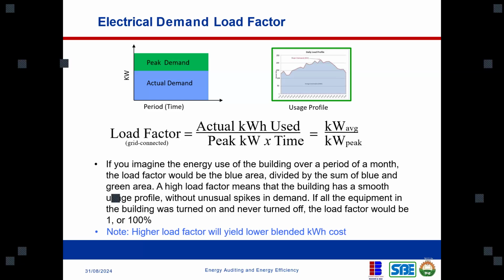So let me give a typical example. If you go into a facility and you see a peak demand in that facility, and that peak demand is, for example, 80 kilowatts, and this demand happens only once in a month. Okay, maybe it's an equipment that they use only once in a month that has introduced this peak demand. When you're sizing your generator, you must size your generator to meet that demand. In as much as it only occurs once in a month, your generator has to meet that demand. What happens actually is that for every other time of the month, that generator is not optimized, it's performing below average, unless that peak demand load comes on.